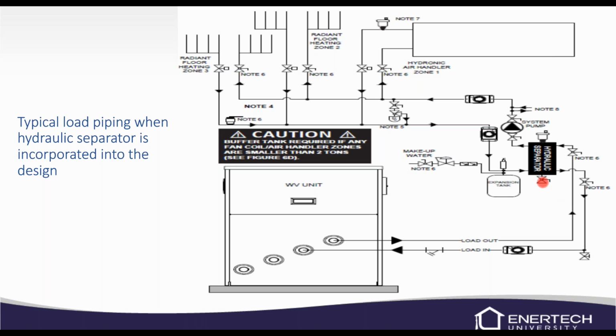There is a little blowdown because it will act as a dirt separator as well, and also an air separator. So there's an air vent. Now, one thing you need to keep in mind when you put in the hydraulic separator is that you will have to add field installed flush blocks to your zoning, as well as an external pump, so that when the zones call, it'll turn this pump on and flow to your zones. And then we have a boiler trim kit, if you're adding makeup water, that kind of thing, right through here. Expansion tank, PRV, check valves, things like that. So this is basically the setup with a hydraulic separator incorporated into the design.